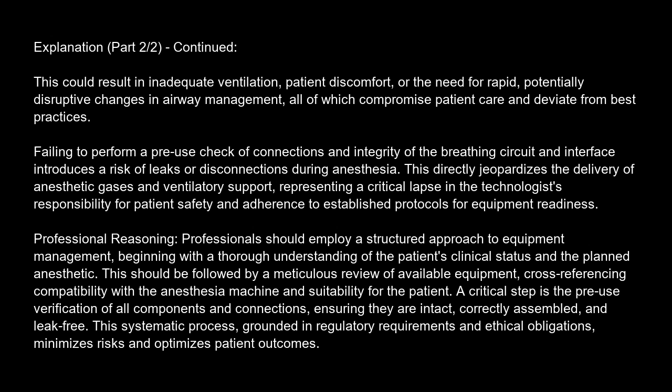Professional reasoning. Professionals should employ a structured approach to equipment management, beginning with a thorough understanding of the patient's clinical status and the planned anesthetic. This should be followed by a meticulous review of available equipment, cross-referencing compatibility with the anesthesia machine and suitability for the patient. A critical step is the pre-use verification of all components and connections, ensuring they are intact, correctly assembled, and leak-free. This systematic process, grounded in regulatory requirements and ethical obligations, minimizes risks and optimizes patient outcomes.